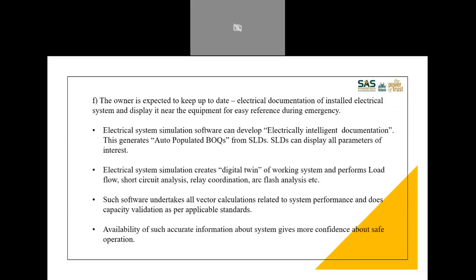The owner is expected to keep up-to-date electrical documentation of the system and display it near the equipment for easy reference during emergency. Now I'll just try to elaborate an example on this. Documentation means exact SLDs and BOQs of all your electrical establishment. Whenever we audit, not always, but at one place we had experienced this, that there was an LT distribution panel with the arrangement for DG also in the same panel. And there were two breakers, one for the transformer, another for the DG breaker, and they were supposed to be mechanically interlocked to each other. When we audited, we saw that the physical interlock was not existing at all.